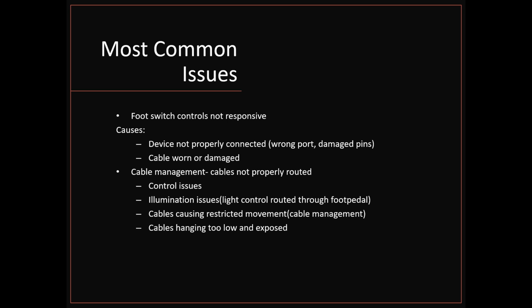If they get a function that isn't working, then it could be either a setting or it could be a switch or something in the foot control that's not responding. We typically will take those in and do a quick exchange. We have a facility in Colorado Springs with techs that are doing nothing but refurbing parts, pedals, XYs, different things like that. So typically when you get a foot switch control that's not responsive, it's either going to be a setting or a switch issue.